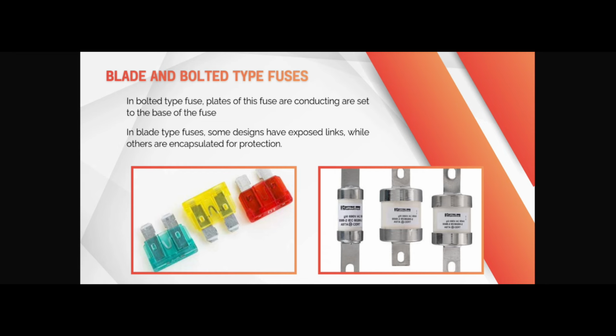So next slide, please. So for the blade and bolted type fuses, these fuses are heavy-duty fuses commonly used in industrial and commercial electrical systems where large amounts of current need to be safely controlled. These fuses are designed to protect equipment and circuits from damage caused by short circuits or overloads. A blade type fuse has flat metal blades or terminals on each end, which make it easy to insert or remove from its holder, similar to how you would plug something in. This design allows for quick replacement and is often used in automotive systems and low voltage electrical panels.